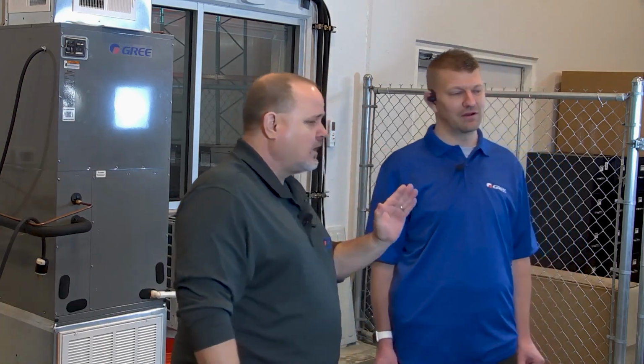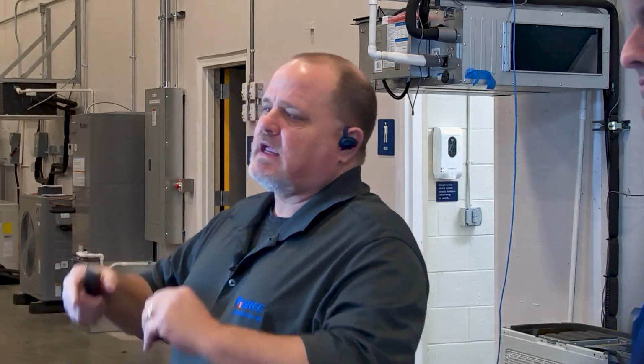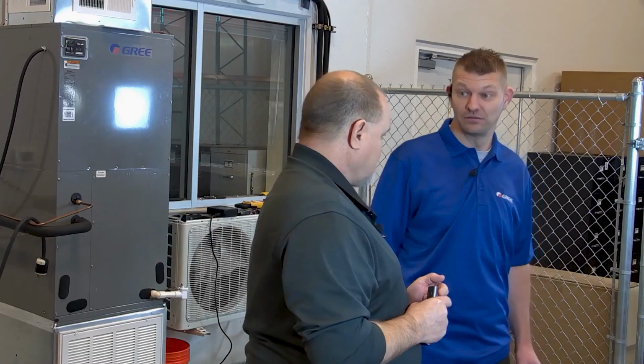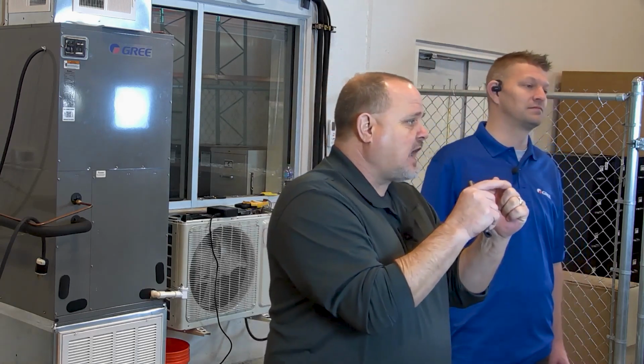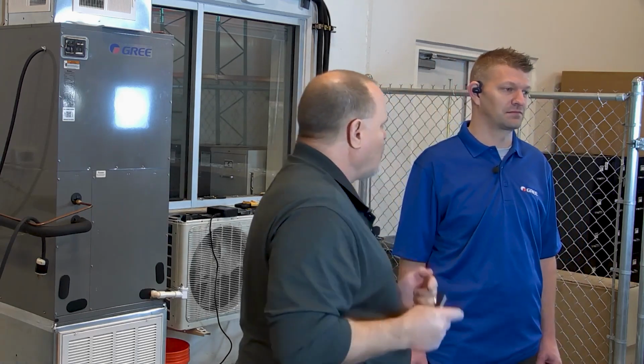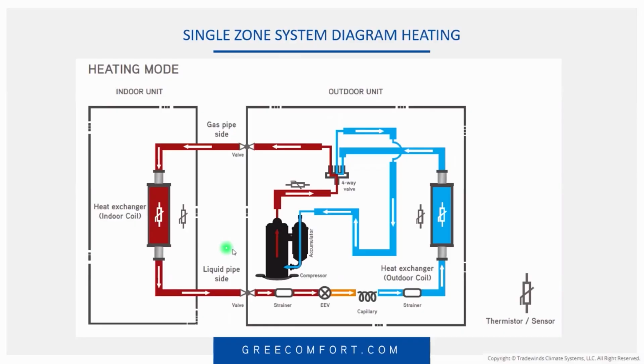So for you guys out there troubleshooting these things, and JD, you've taken the phone calls too. Oh yeah. Every time you pick up that remote and make a change, you're making the whole system have to rethink. It has to relearn. So you've got to give that machine time to relearn what you just told it to do. Even though all you did was make a temperature change on the indoor unit, it's not going to be immediate. The whole board out there is going, oh, wait a minute. We just increased our demand from a 10-degree demand to a 15-degree demand. Whoa, man, okay. Now what do I do with that?